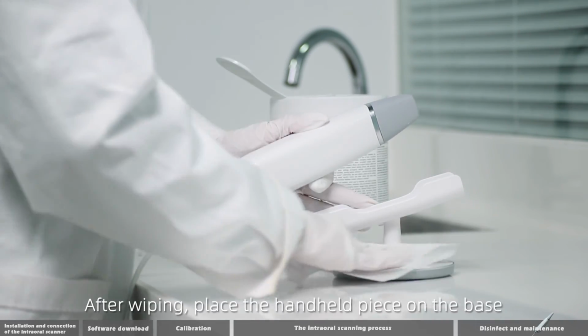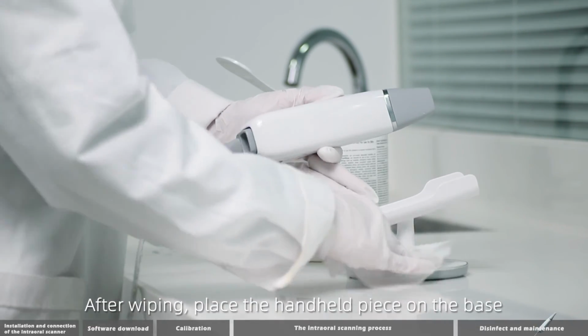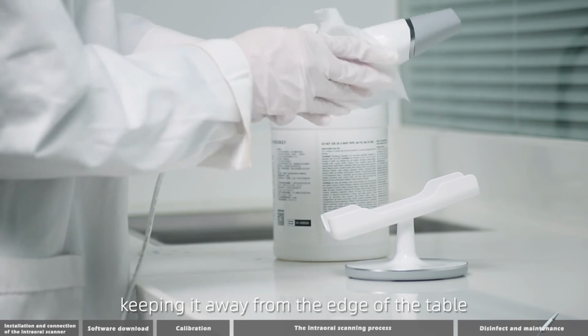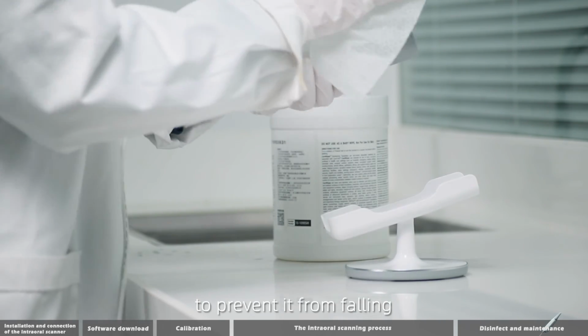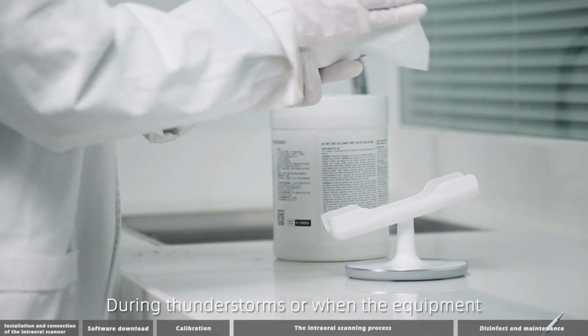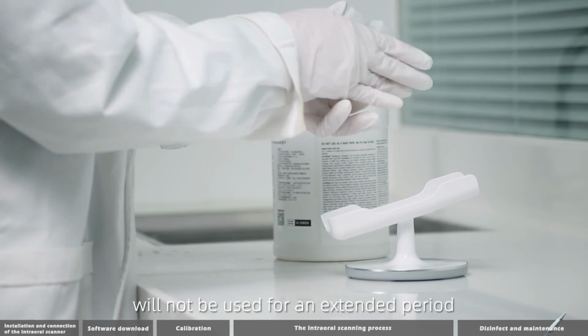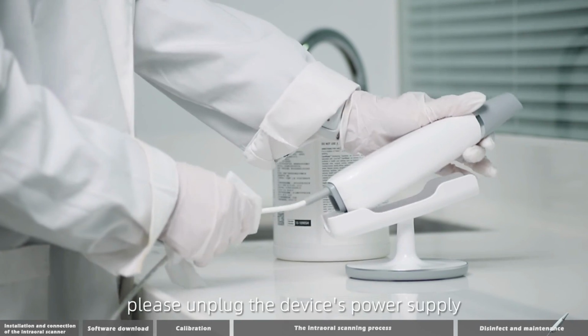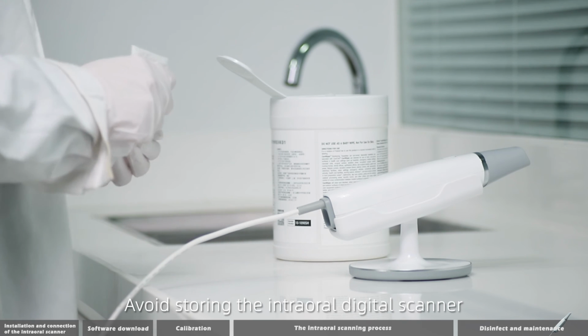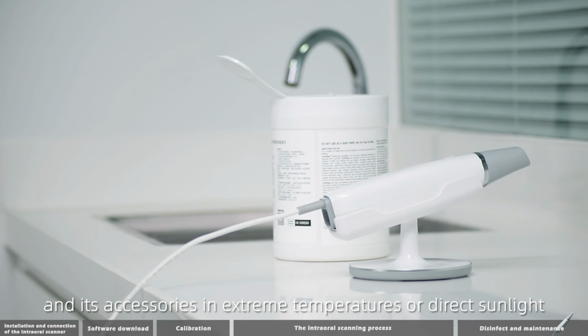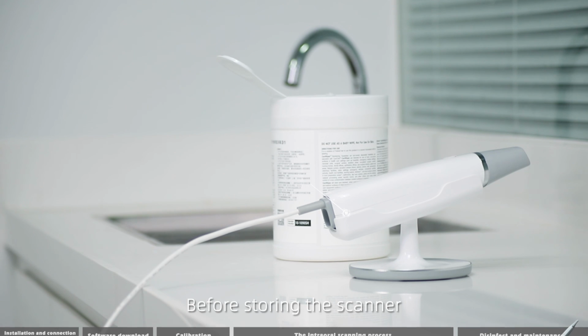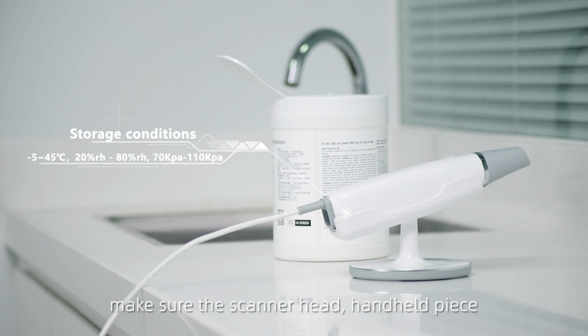disinfection. After wiping, place the handheld piece on the base, keeping it away from the edge of the table to prevent it from falling. During thunderstorms or when the equipment will not be used for an extended period, please unplug the device's power supply. Avoid storing the intraoral digital scanner and its accessories in extreme temperatures or direct sunlight. Before storing the scanner, make sure the scanner head, handheld piece, and base are completely dry.